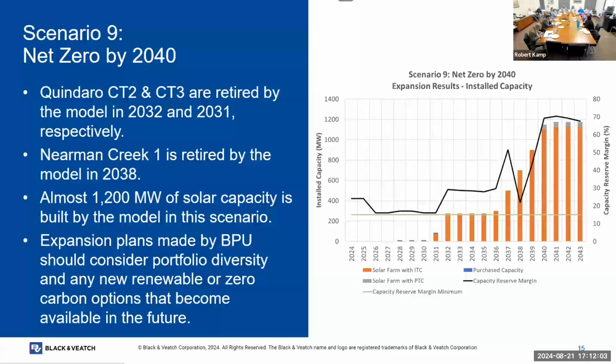So one of the challenges with this approach, obviously, is it looks only at the assumptions that we know exist today. And so as we build out 1,200 megawatts of solar, what are all the other utilities and other companies within SPP doing? And so that will impact the ELCC, or effective load carrying capability, in Kansas and SPP, just like it has in California today, right? The effective load carrying capability in California is much, much lower because they have so much solar already today, which is just what we've seen on the wind side, right? That's why you're not seeing wind pop up: the effective load carrying capability is so much lower with wind today because we've had that build out.